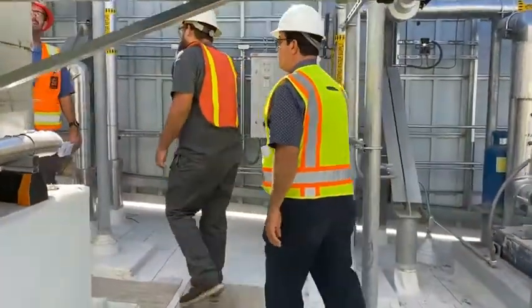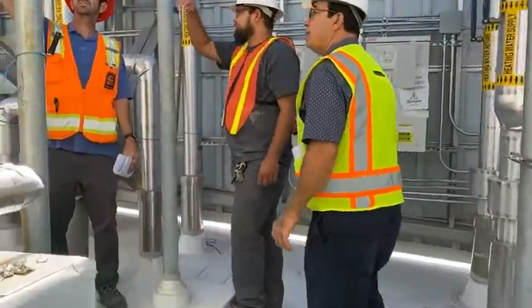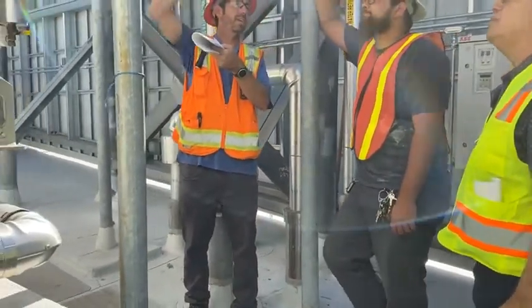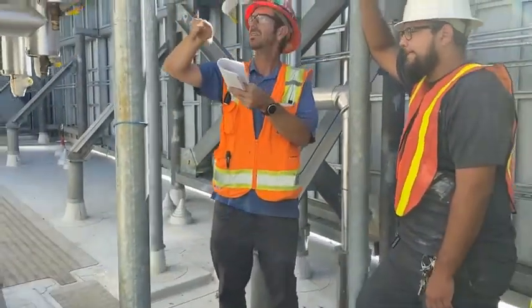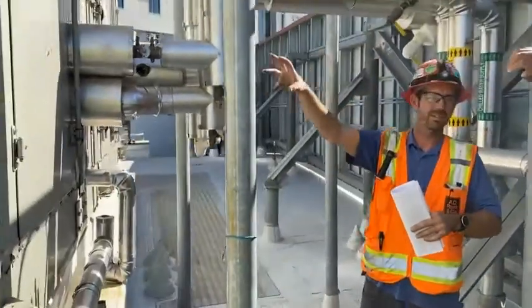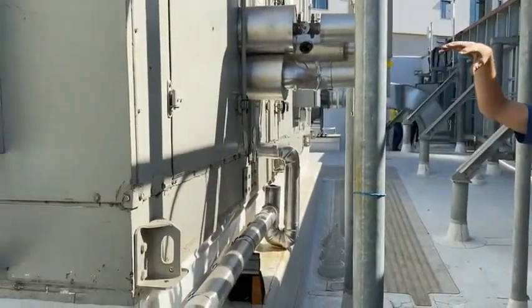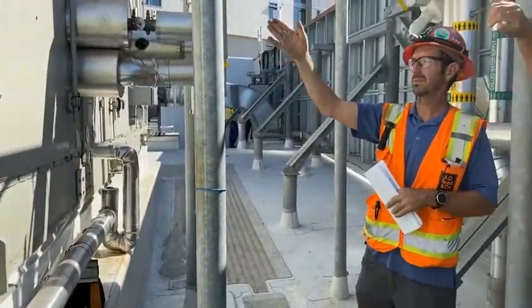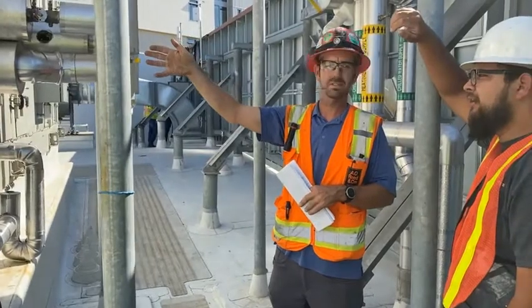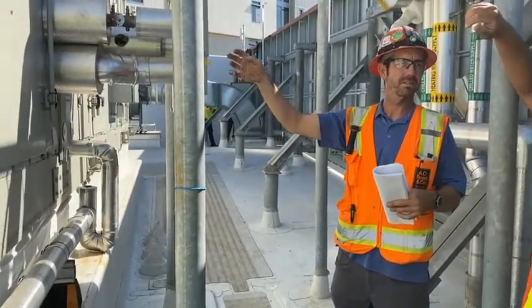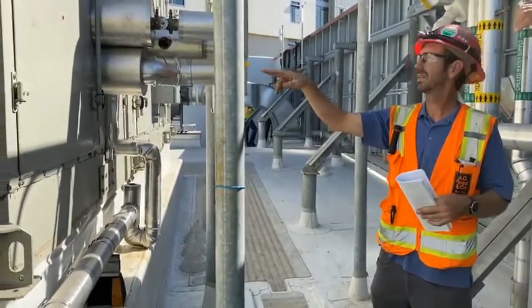And then this air handler is set up the same. We have the outside air filters. We have the canisters for the outside air. There's the 6, I think this one might have 8. There's still the canisters. That's where the flow stations are. Then we have our filters. We have the MERV 8s, then the MERV 13s. They can be cartridge or box as long as they're a MERV 8 and a MERV 13.